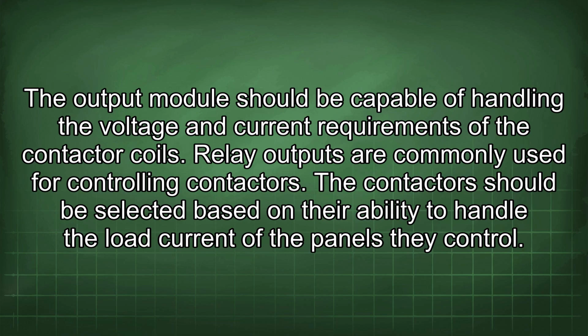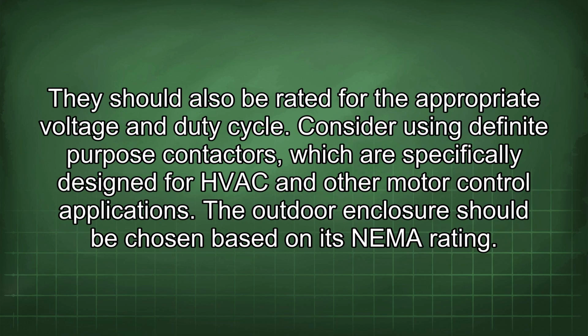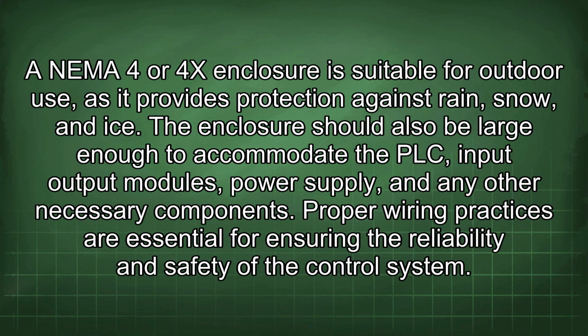The contactors should be selected based on their ability to handle the load current of the panels they control. They should also be rated for the appropriate voltage and duty cycle. Consider using definite purpose contactors, which are specifically designed for HVAC and other motor control applications. The outdoor enclosure should be chosen based on its NEMA rating. A NEMA 4 or 4X enclosure is suitable for outdoor use, as it provides protection against rain, snow, and ice. The enclosure should also be large enough to accommodate the PLC, input-output modules, power supply, and any other necessary component.